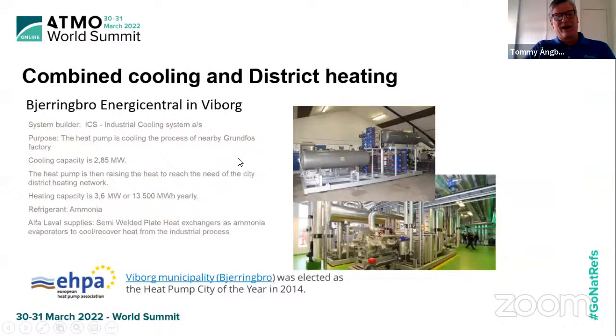And here you have combined cooling, and this is interesting because here we are using not only the heat, but we benefit from the cooling of a process at the Grundfos factory in Denmark. And the system builder ICS installed a cooling capacity of 2.85 megawatt, used as a heating input to the heat pump, and then could produce 3.6 megawatt of heating yearly to the district heating network. So we are supplying the semi-welded heat exchangers as evaporators to recover this heat from the industrial process.